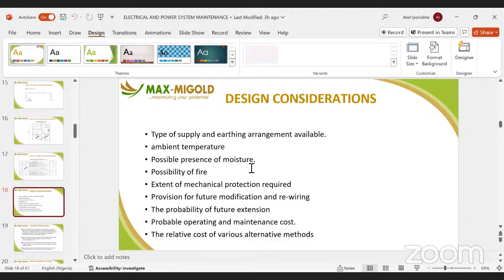The temperature involved also matters - the generator you recommend in Lagos will be different from the one you recommend in Maiduguri. Maiduguri is very hot, Lagos is cold and full of moisture. So you may need a soundproof generator in Lagos to prevent salty water getting in and damaging equipment. But in the north, you may not need soundproofing because their place is very hot - you even need to open the generator for cross ventilation, free flow of air into it. Possible presence of moisture, I explained this.